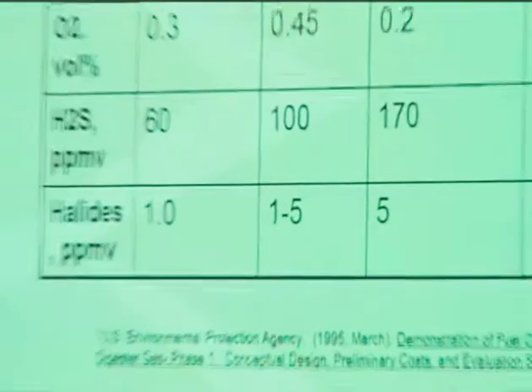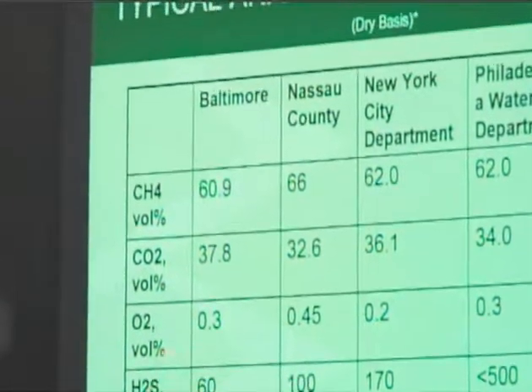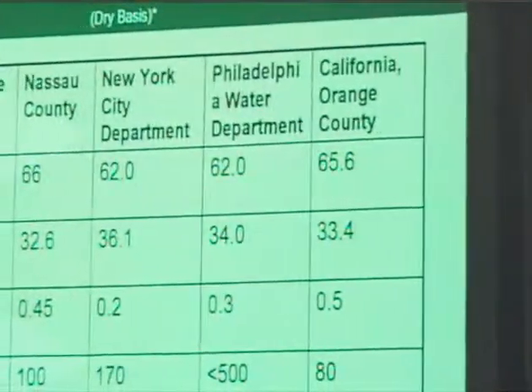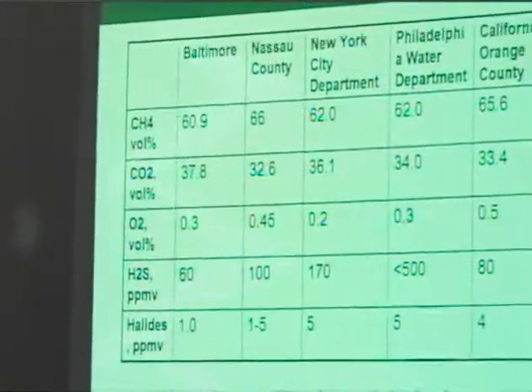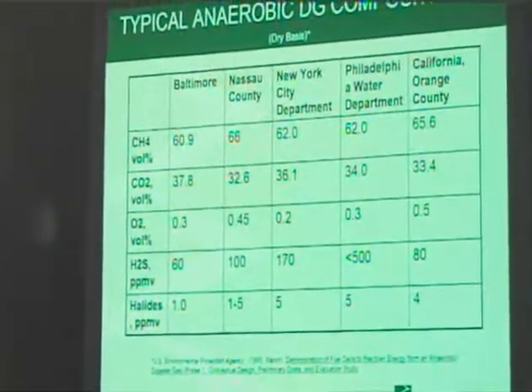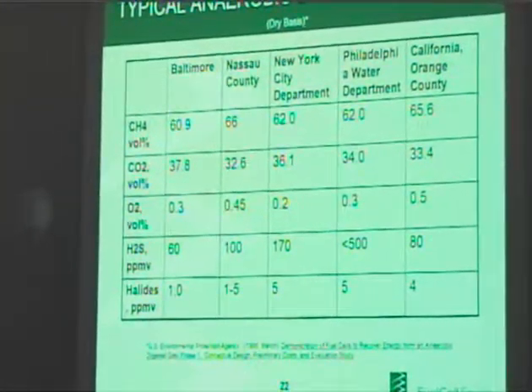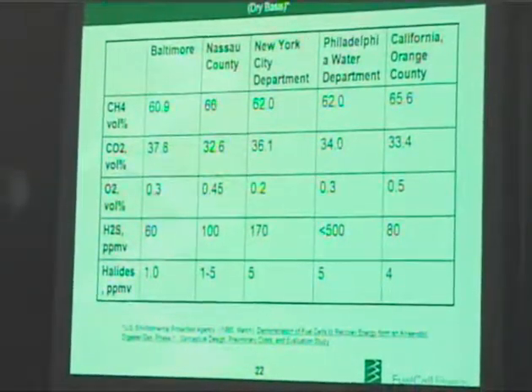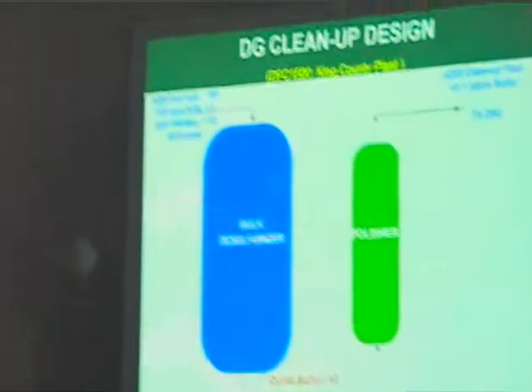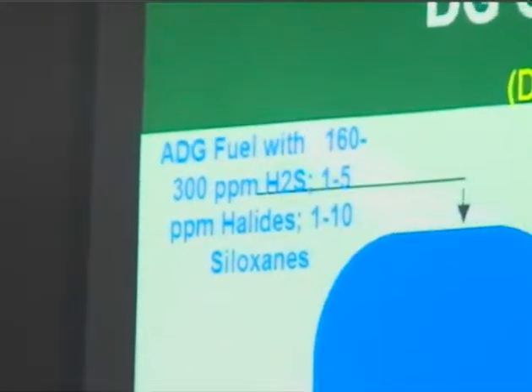Again, the digester gas composition depends on where you are getting it, and it can vary significantly in fuel quality. Especially I wanted to point out the contaminants - one gas is at 60 ppm and it can go as high as 500 ppm. Therefore, you have to have a system that can treat a wide range of contaminants, including halides, which can go from 1 ppm to 5 ppm. These are all important issues when contaminants exceed the 100 ppb level.